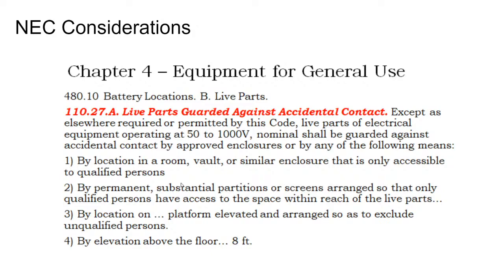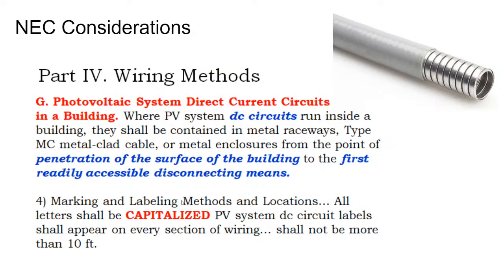High voltage batteries do have code-mandated physical protection requirements. On the solar side, our DC circuits are mandated to be in metal conduit. For physical protection reasons, not for grounding, I could easily see this metal conduit requirement making its way into battery conductors as well, requiring more protection than just plastic conduit when inside a building.